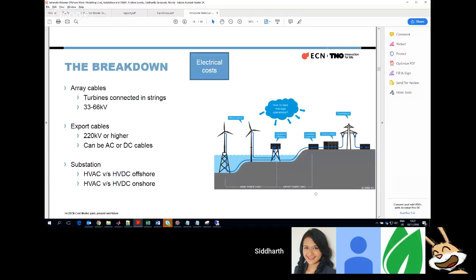It's also necessary to come up with the capex cost of these components. Now, there are different factors that can vary this. For instance, if the wind farm is really close to shore, and if there are fewer wind turbines in the farm, we might not need the offshore high voltage substation—we can just do with array cables and the onshore substation. But generally, now that wind farms are quite far away, we need one or maybe even two offshore substations.